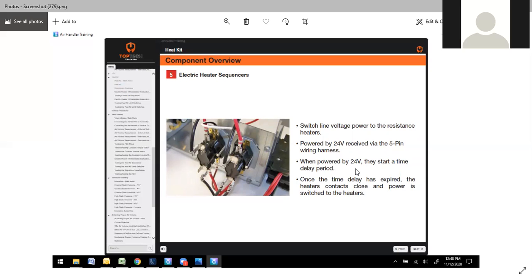You'll also have the same reverse cycle. So when you lose the call for heat, it starts a downtime cycle. So one element will clear, then another, another, and another. And if you put your amp meter on your line voltage side, you can actually watch that happen. You can actually watch each element drop out or pop in as they engage.